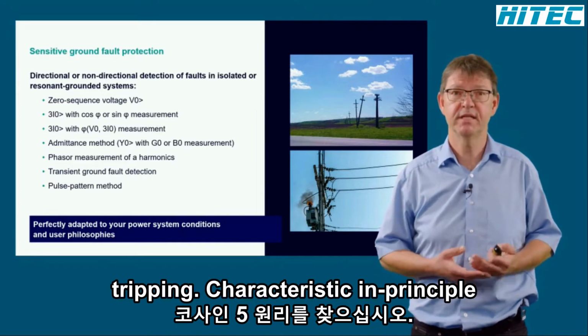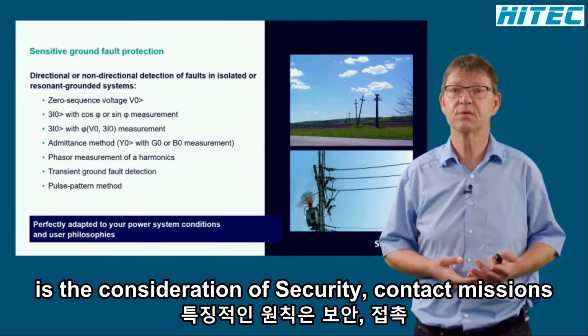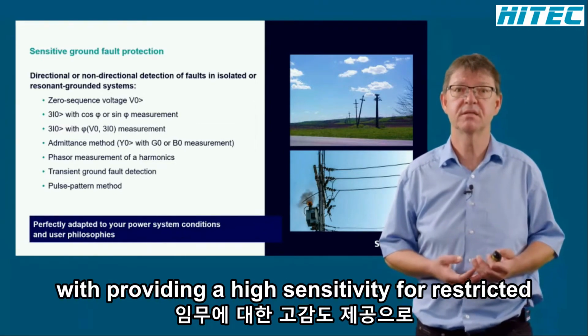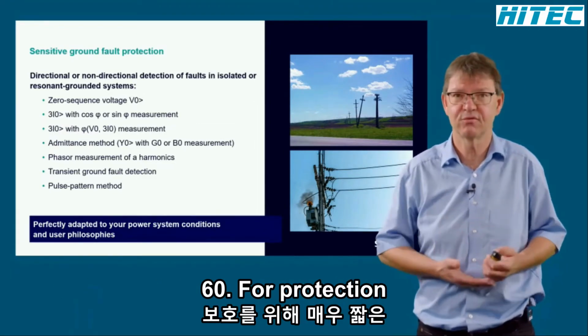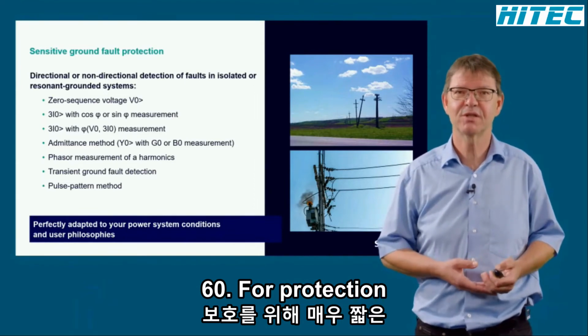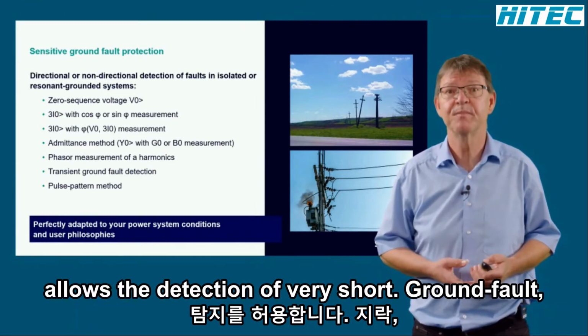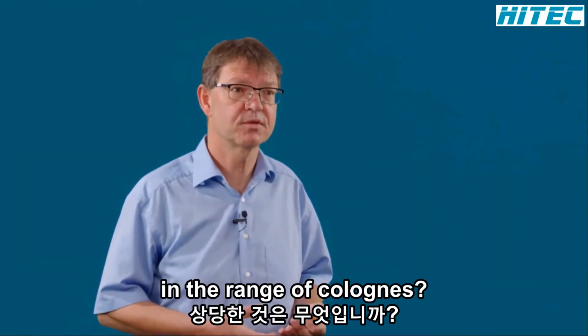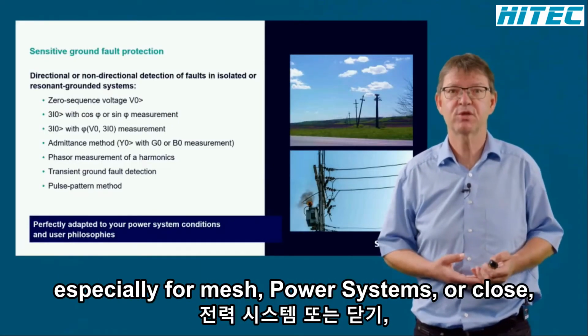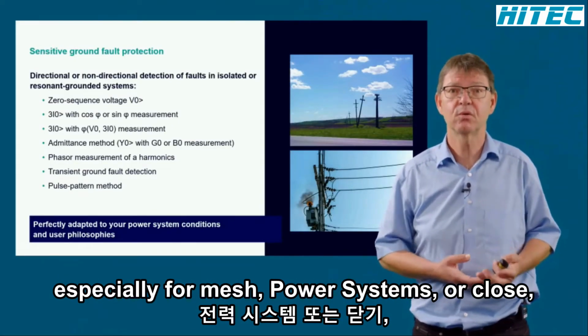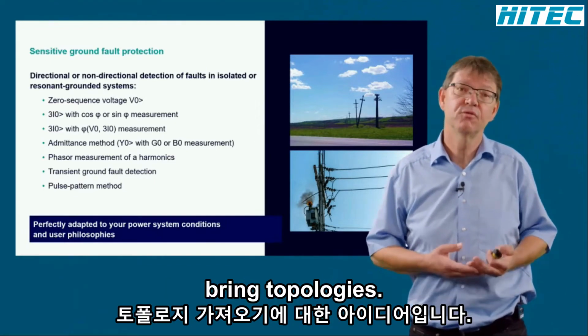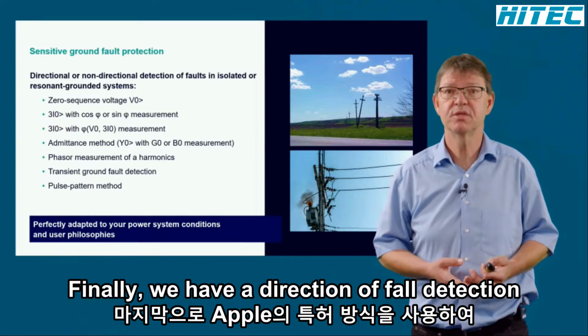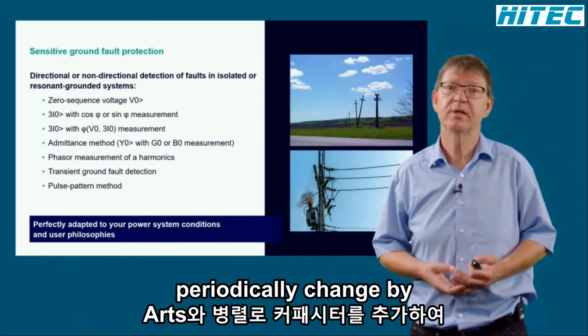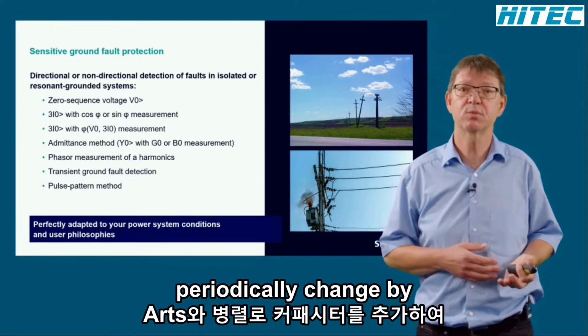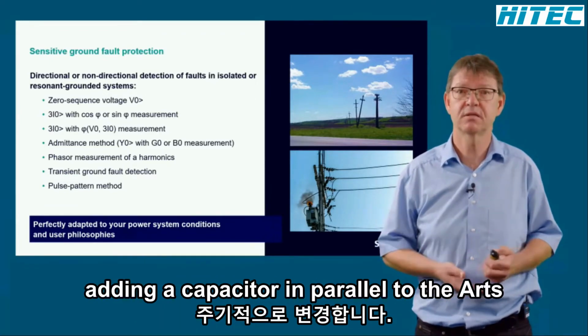A variant of the phase angle measurement principle is the consideration of zero sequence admittances, providing a higher sensitivity for resistive faults. The transient ground fault protection allows the detection of very short ground faults, even transient faults, also with considerable fault resistances in the range of kiloohms. This function is ideal especially for mesh power systems or closed ring topologies. Finally, we have a directional fault detection using a pulse pattern method. Here the amplitude of the fault current is periodically changed by adding a capacitor in parallel to the arc suppressing coil.